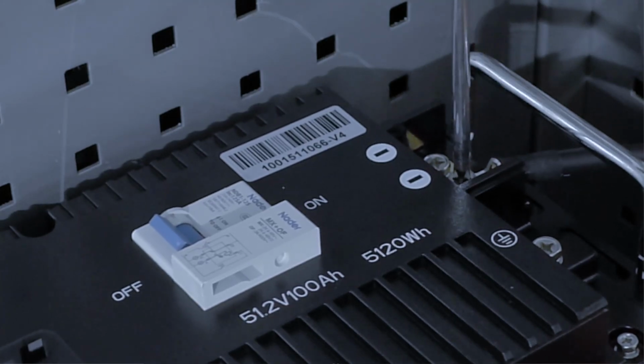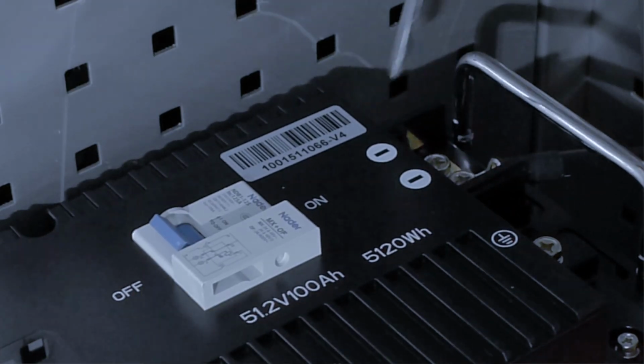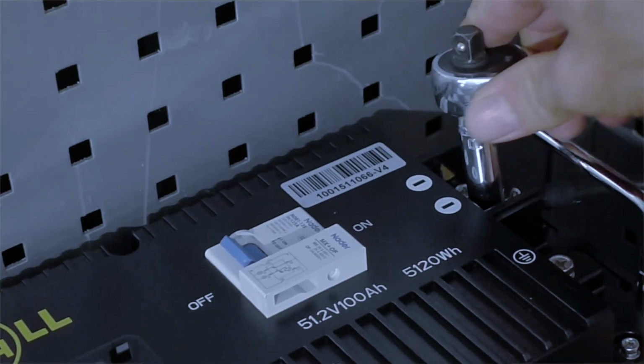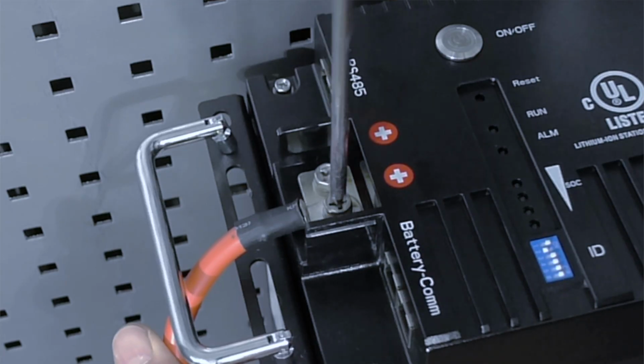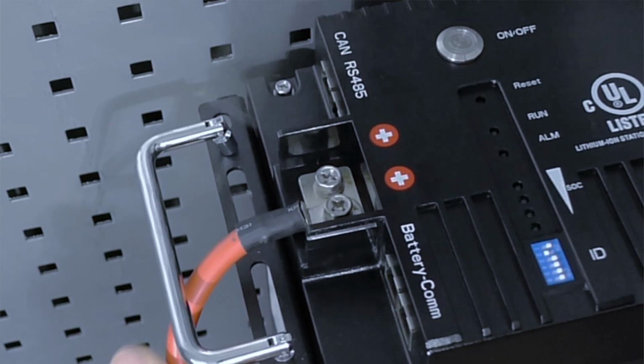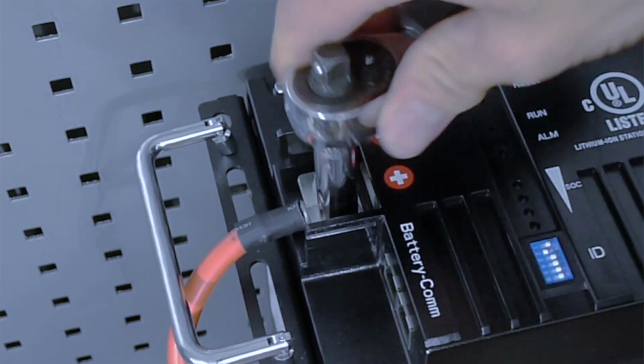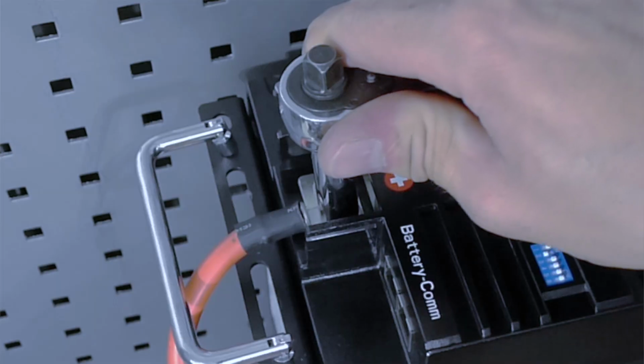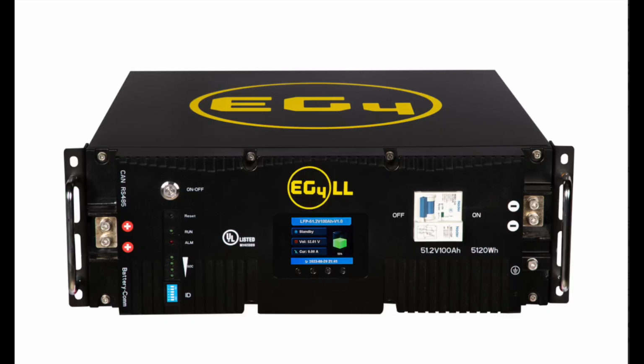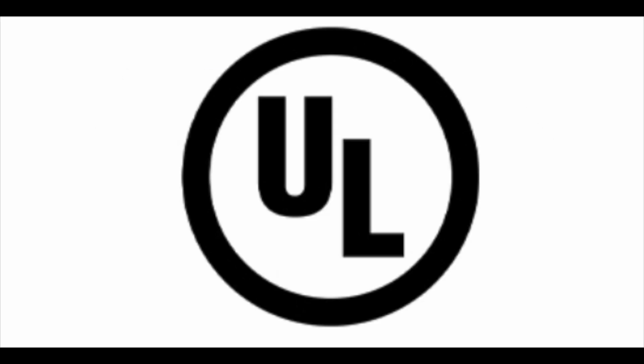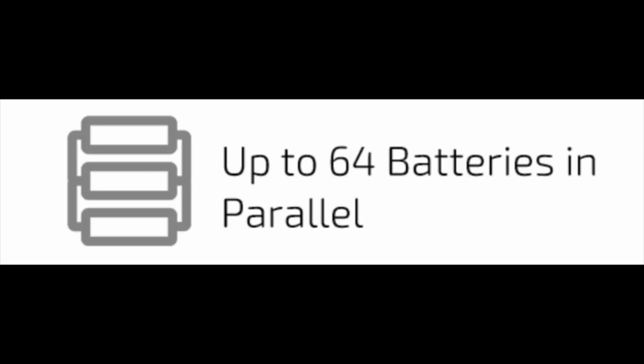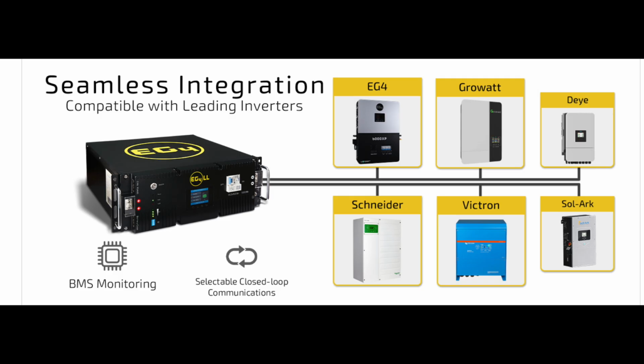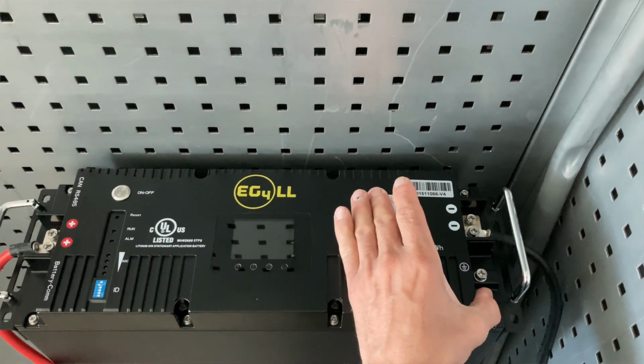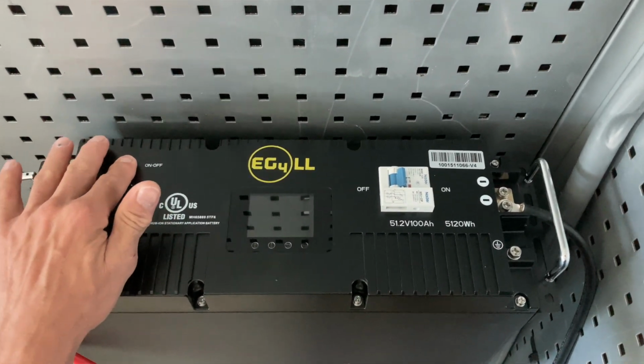We wired all the components together, let's connect the battery as well. We are connecting the black cable to battery's negative and the red cable to battery's positive terminal. This is the EG4 LLS 48V 100 Ah server rack battery, have a life cycle of more than 15 years with a 80% depth of discharge daily. Charge and discharge current is up to 100 amps. UL listed, parallel up to 64 batteries and comes with a LCD touchscreen. Supports closed-loop communication and enjoy the 10-year warranty. Let's turn it on and see how it looks.